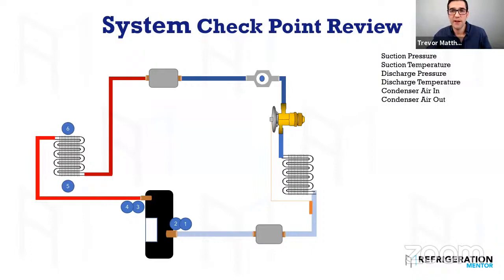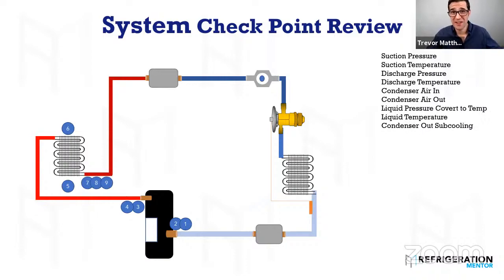So condenser air in, condenser air out. What should it be? This here is called the delta. And then there's a TD. So you need to understand the differences between delta and TD. For me, the delta is the room temp, and for the TD, it's the room temperature and the SST. That's your TD. Okay. Then you need to get your subcooling at your condenser. Every time you've got to check what's that liquid coming out, because you need to make sure you have a full column of liquid leaving that condenser.